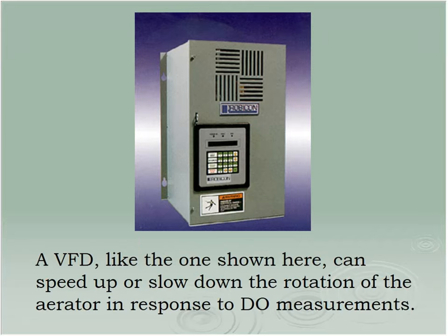Ideally, because electricity is so expensive, particularly in this part of the country, and we're using so much of it, you'll have a control loop in there. You'll have a dissolved oxygen meter in the tank, and you'll have a control loop set up. So they say, I want to control it at 2 milligrams per liter, and this will sense what's going on in the tank, and it either speeds up the blowers or slows them down. So you don't put in any more energy than you need to, but you always get what you do need.